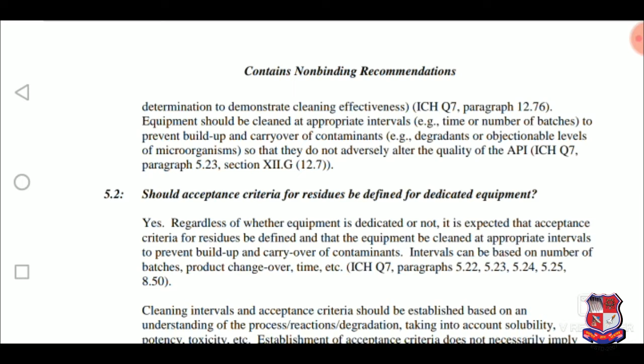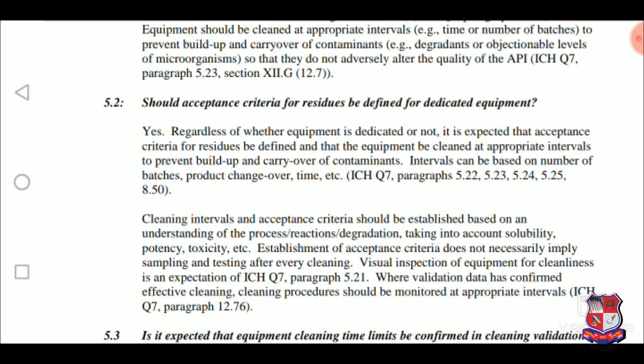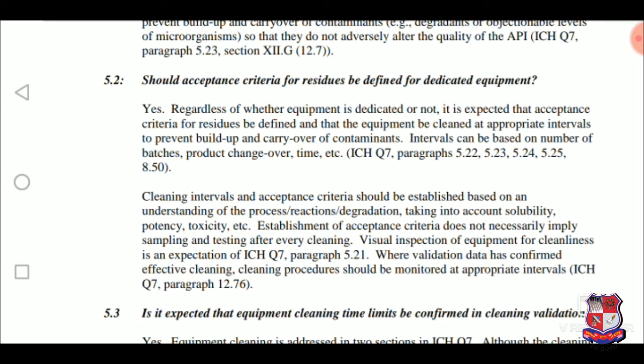Should acceptance criteria for residues be defined for dedicated equipment? Yes. Regardless of whether equipment is dedicated or not, it is expected that acceptance criteria for residues be defined and that the equipment be cleaned at appropriate intervals to prevent buildup and carryover of contaminants. Intervals can be based on number of batches, product changeover, time, etc. Cleaning intervals and acceptance criteria should be established based on an understanding of the process, reactions, degradation, taking into account solubility, potency and toxicity, etc.